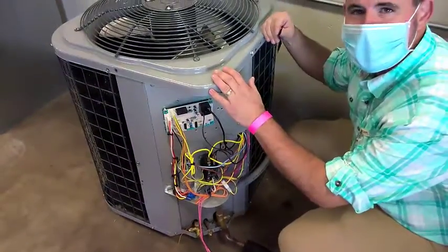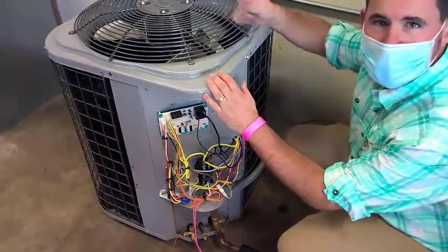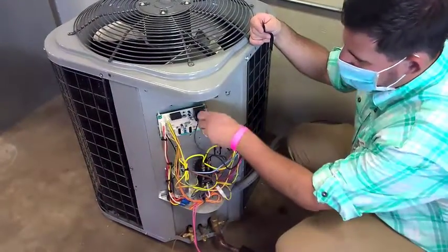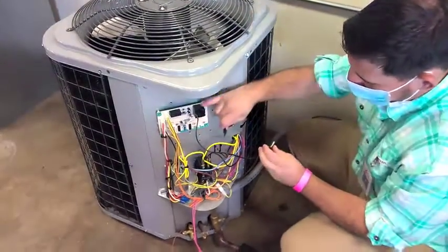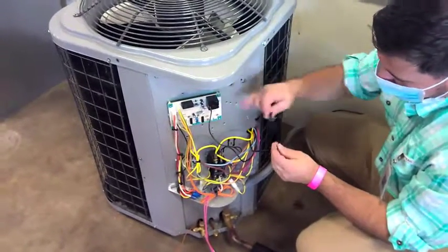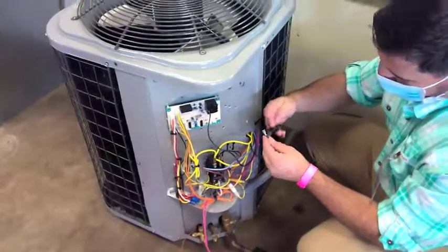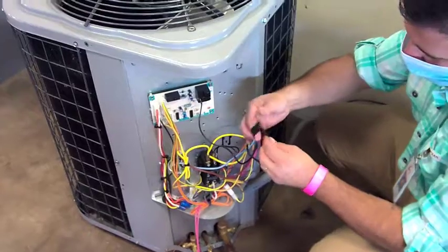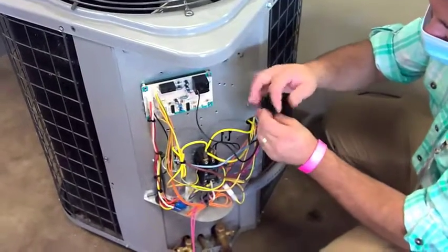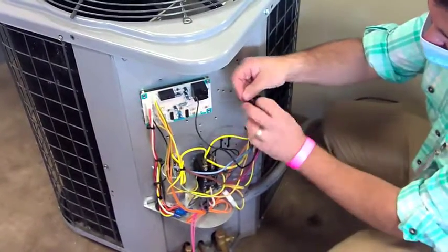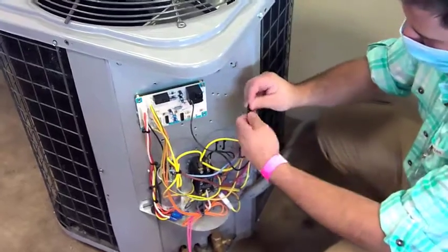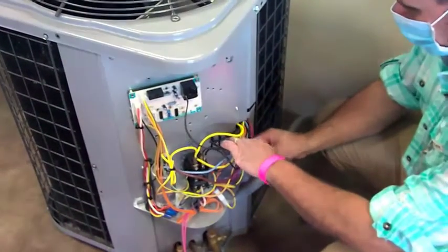But in order to freeze it, I'm going to have to disconnect power to my outdoor fan motor. So I'm going to remove the common wire coming off of my fan motor going to my relay to make sure my fan doesn't try to kick on. You always want to tape it up because it will have back voltage on it. I'll tape it up, tuck it out of the way.